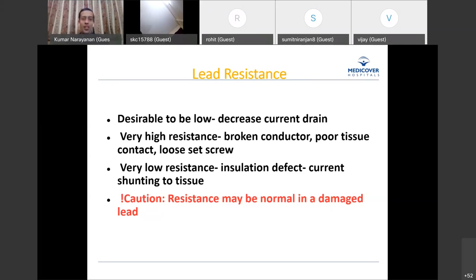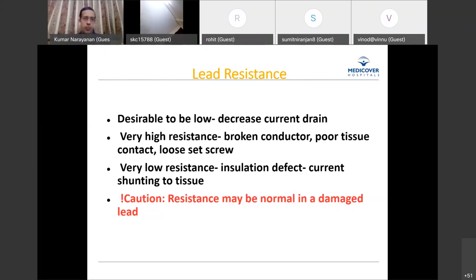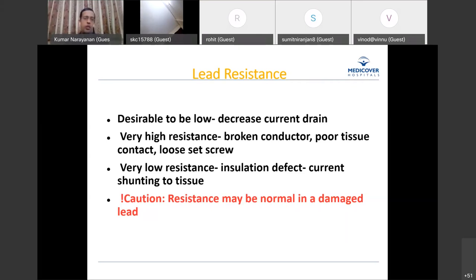A normal resistance does not completely rule out a damaged lead. Micro-breaks in the conductor can cause intermittent contact — the wires can touch and move apart repeatedly. At a given moment, resistance may appear normal even with a malfunctioning lead. If you find a very abnormal resistance, something is wrong. But a normal resistance when encountering problems should not immediately reassure you — you still need to test other parameters.